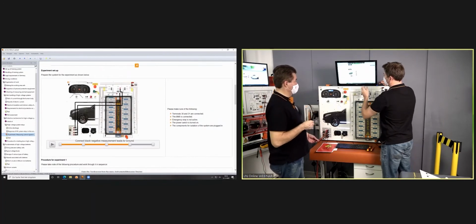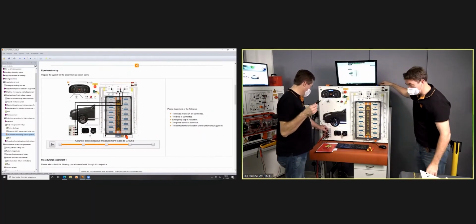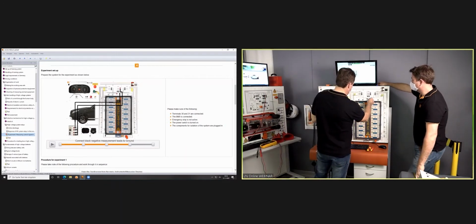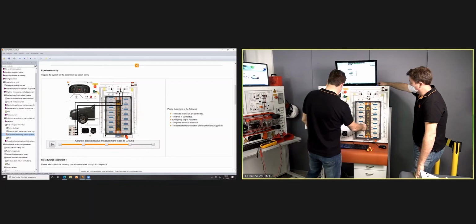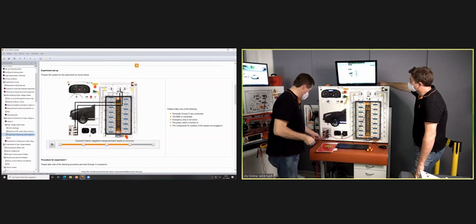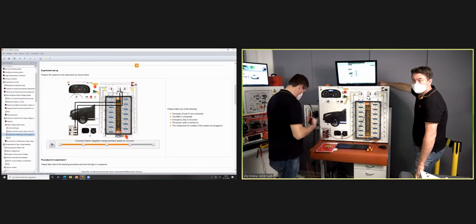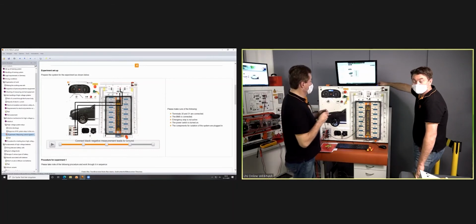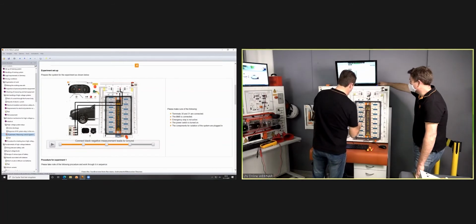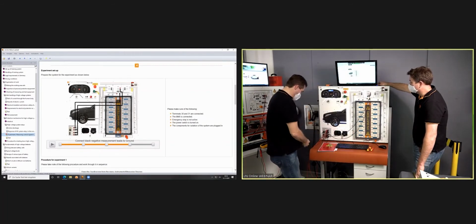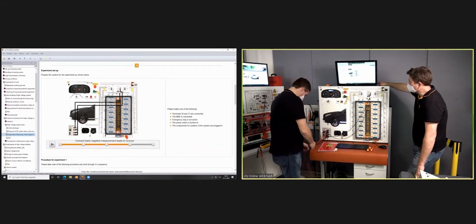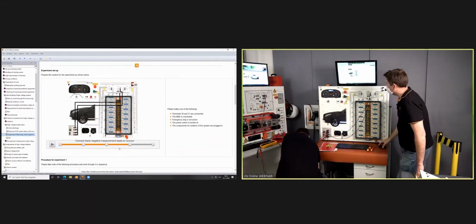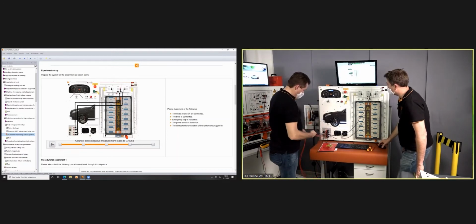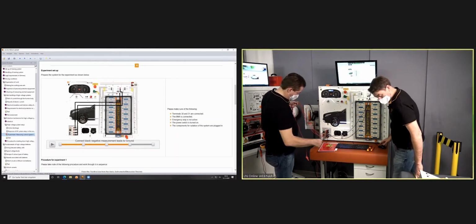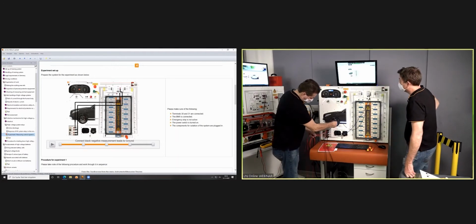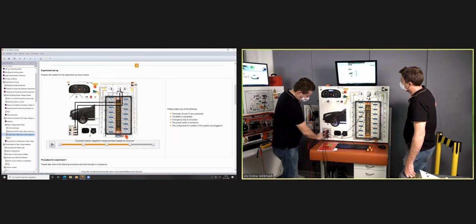Okay, minus. The first step was channel A minus to HV minus. Then was the second ground connection to the minus of the low voltage system, the 12 volt level. They are interconnected. You can see that on the oscilloscope input, that all of the grounds for the system main relays we're going to check are all together.